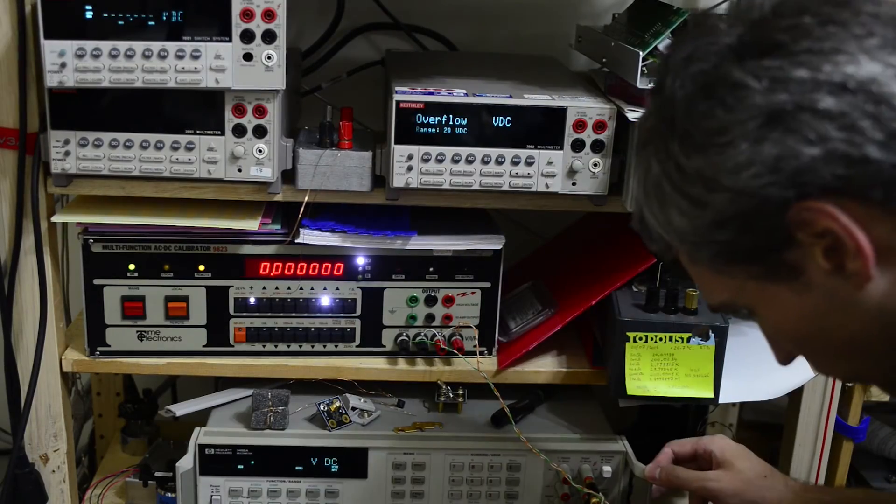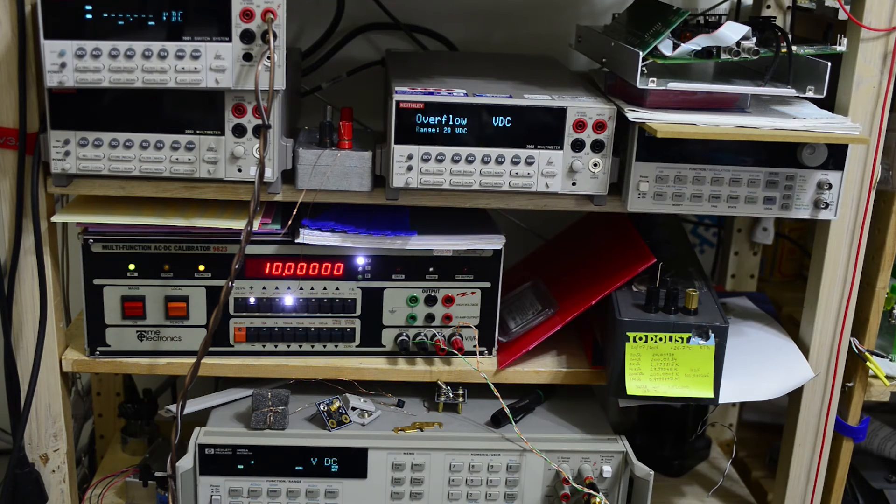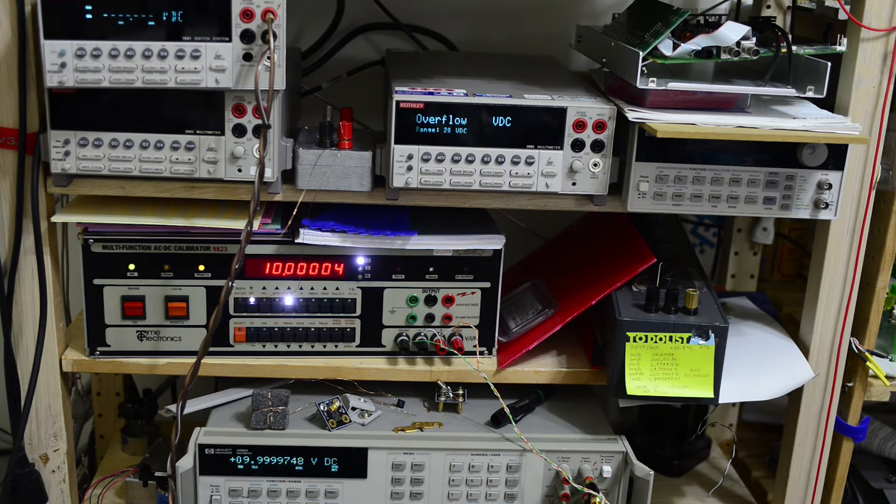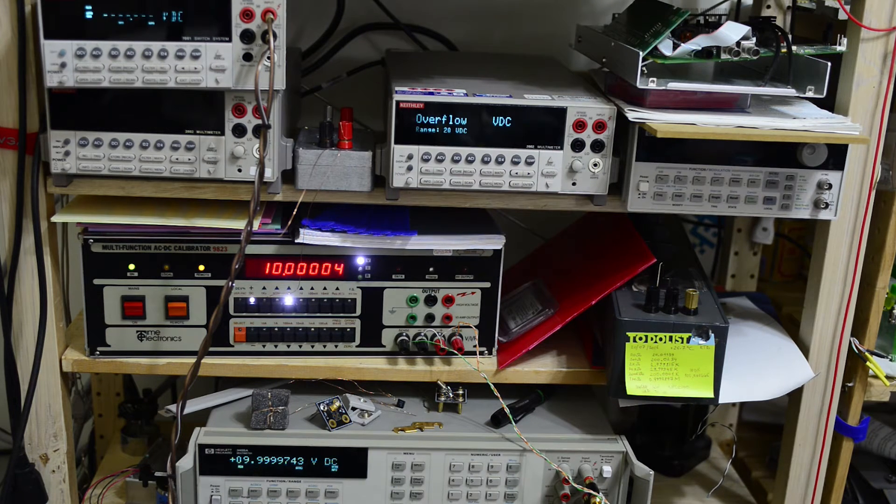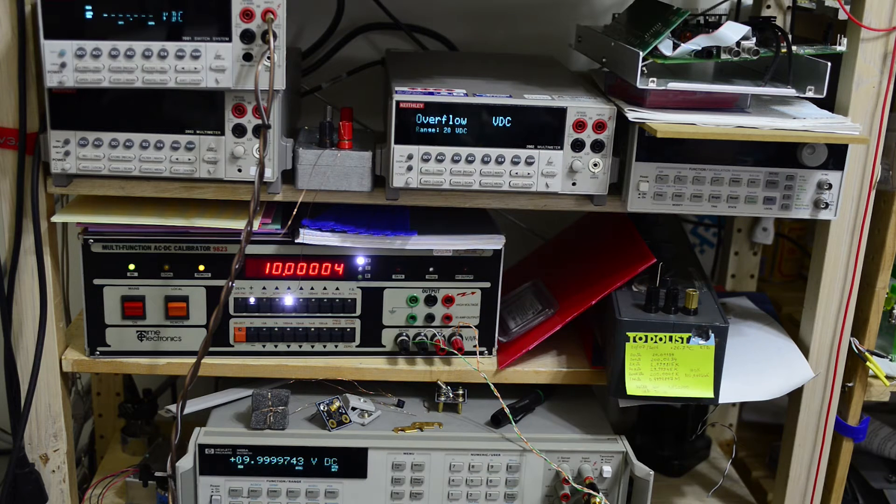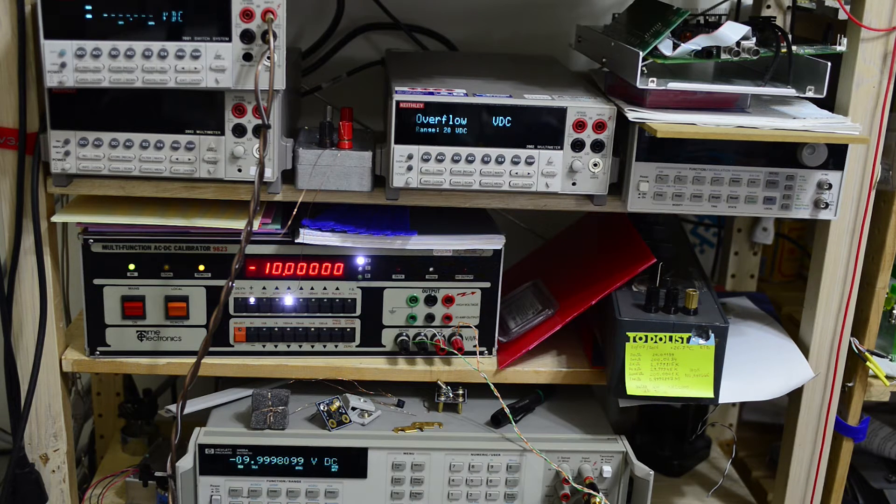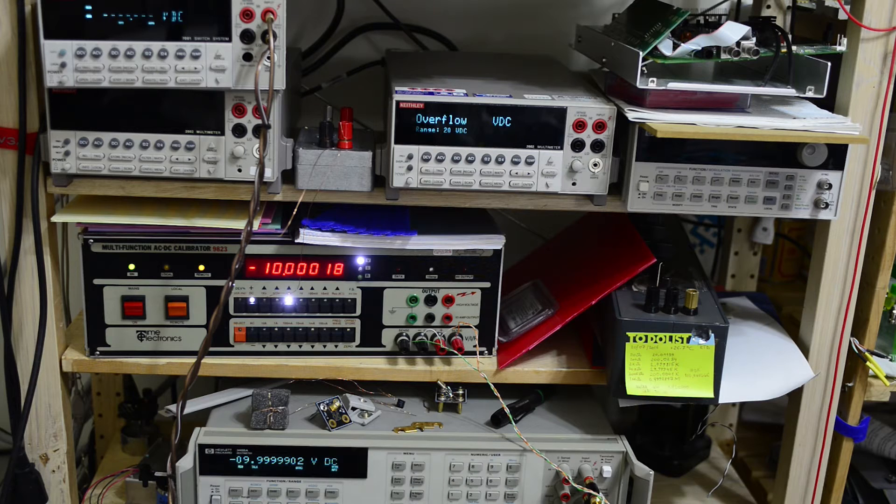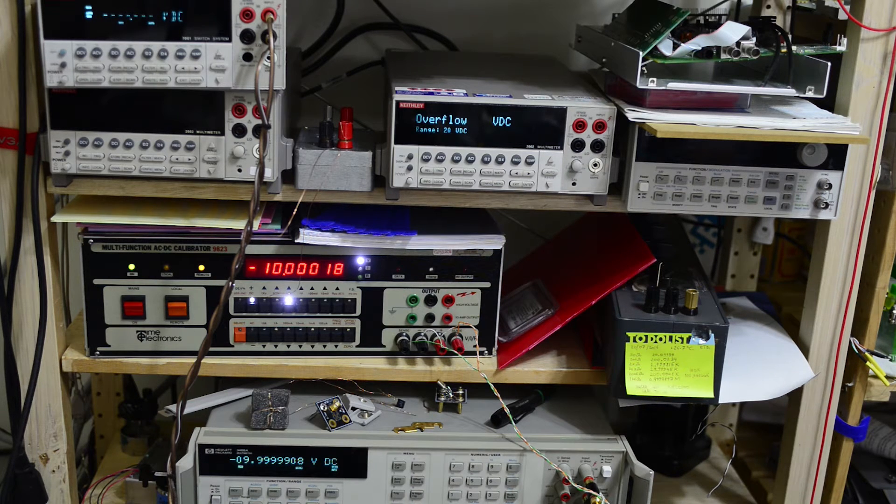Next step is calibration with open when nothing is connected to the meter. And then three steps for DC voltage calibration. So I'll connect a 10 volt source to both HP and Keithley meter and use the value from HP meter as reference.